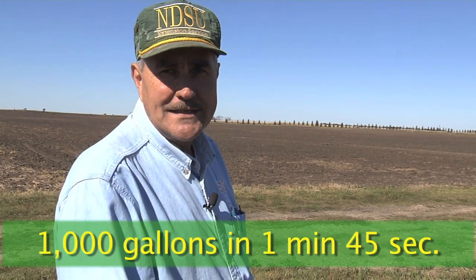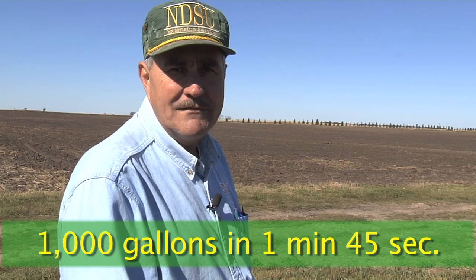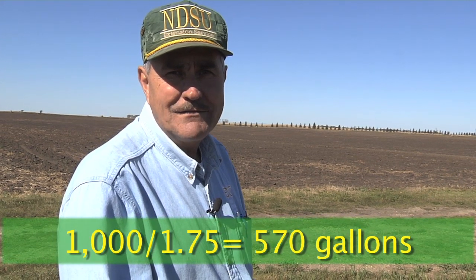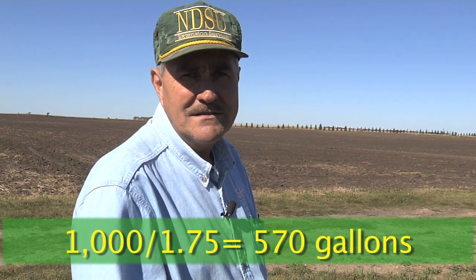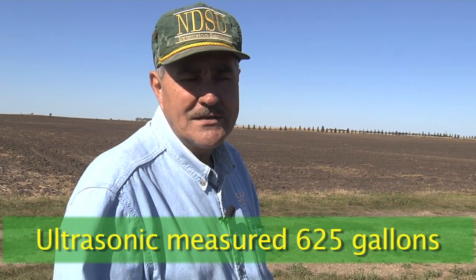If I calculate the flow rate using this meter, it said I pumped 1,000 gallons in 1 minute and 45 seconds, and 45 seconds is 3/4 of a minute. So if I divide 1,000 by 1.75, that comes out to about 570 gallons a minute. Now we just measured with our ultrasonic, and it shows that this pump is actually putting out 625.